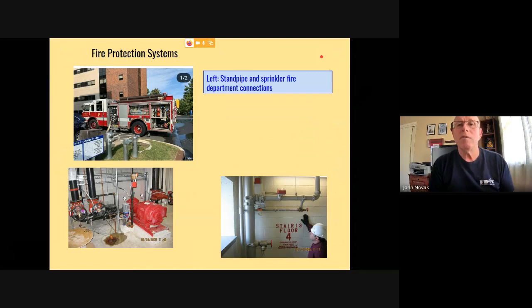So to the left is a standpipe and sprinkler fire department connection. So there are numerous fire department connections here, right? One I believe is for the sprinkler, one is for the standpipe. There's signage over here that's going to tell the pump operator or the chauffeur what system to hook to if he knows the fire is located in a different part of the building. This over here is a fire pump test header. So again, we don't want to touch this. This is only for testing the fire pump.